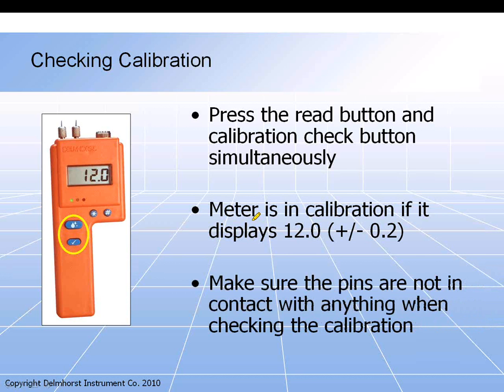Again, this is just an in-field check that the meter is in calibration. It's not necessary to do it every time you use the meter, but it's a nice feature just to check it periodically to make sure it's calibrated. Our guideline is if it falls outside of that 12%, or 11.8 to 12.2, the first thing to do would be to change the battery. If with a new battery the meter is still not calibrating or checking calibration, it does need to come back for service. That's just one thing to keep in mind there.